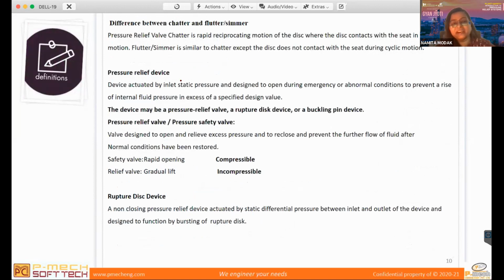So pressure relieving devices, sometimes you have heard, people also call pressure safety valves. So the terminologies are only different. It is based on the type of the fluid which you're relieving. If you're relieving a liquid, which is an incompressible flow, then it's called the pressure relief valve. And when you are relieving a compressible fluid, it's called the pressure safety valve. So that is the only difference between these two terminologies. Otherwise, the sizing and all other scenario considerations are the same.